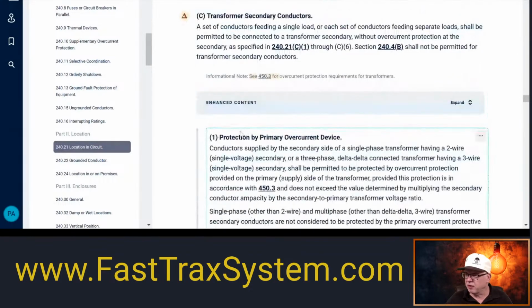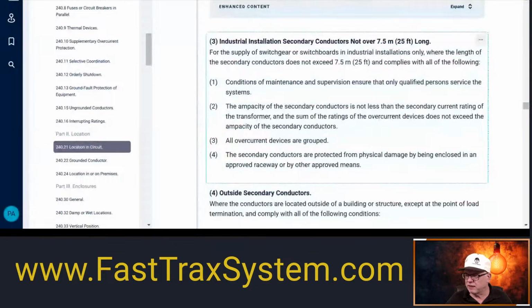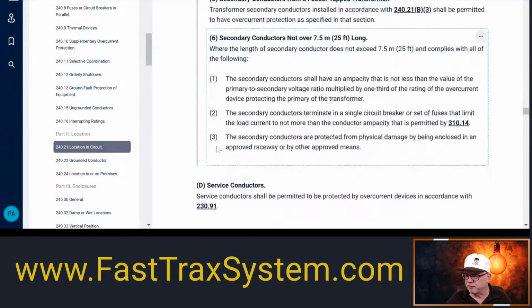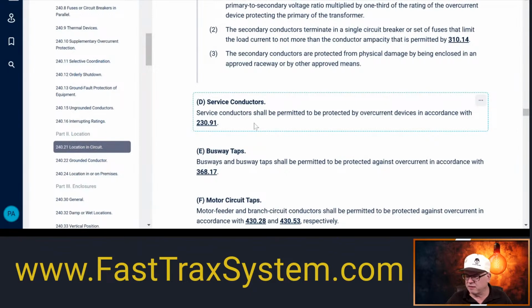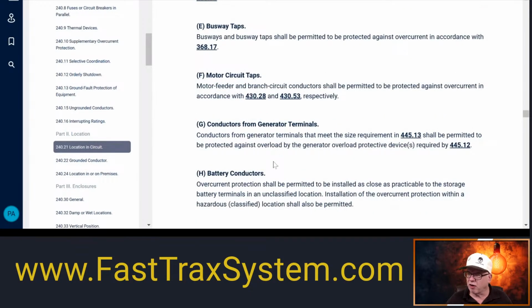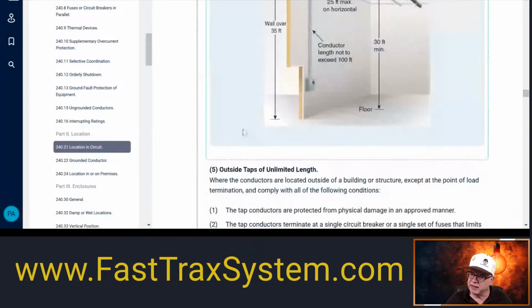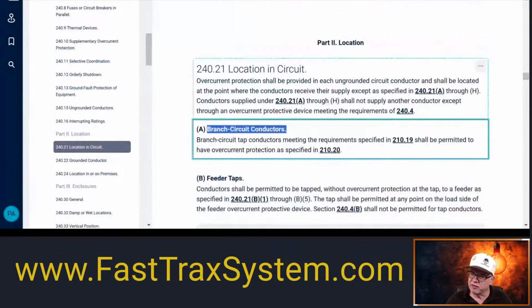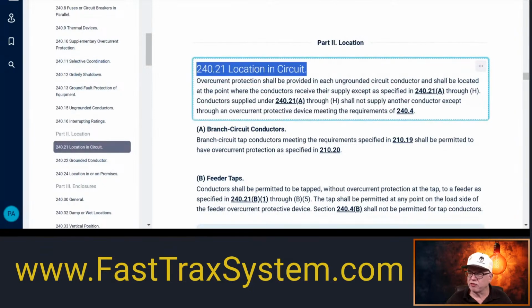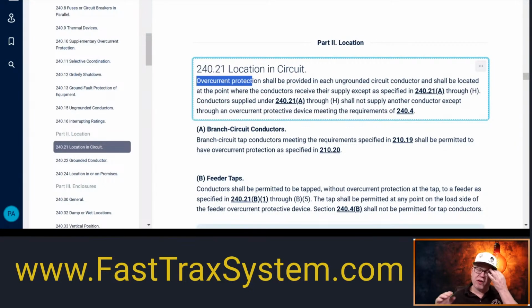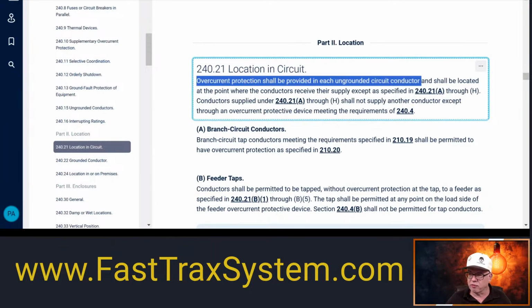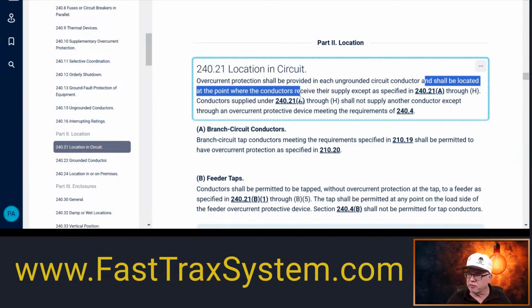All right. I don't think there is anything else that we want to cover today with these. There are other applications for taps, by the way, just so you can see. Let me go back up here. So this is basically the location. Overcurrent is in 240, right? So it's really all about where there's overcurrent protection and where there's not, when it comes to the conductors. So overcurrent protection shall be provided in each ungrounded circuit conductor. That's the general rule. We have to have overcurrent protection, and it shall be located at the point where the conductors receive their supply.